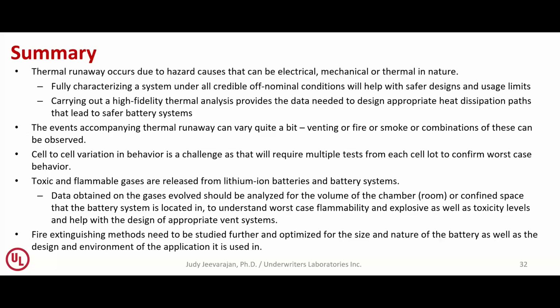To summarize, thermal runaway can occur due to different hazard causes, mainly categorized as electrical, mechanical, or thermal in nature. It's very important to fully characterize the system under all credible off-nominal conditions. This helps you understand your limits for battery design, so you can put controls and limits in place and recommend usage limits.